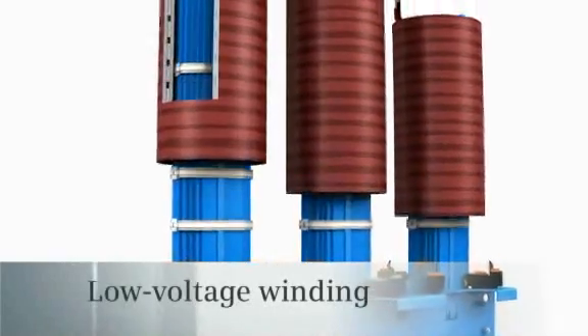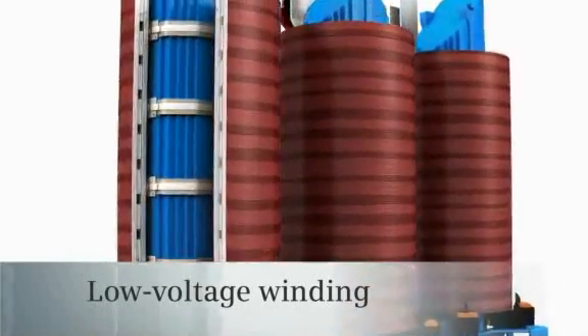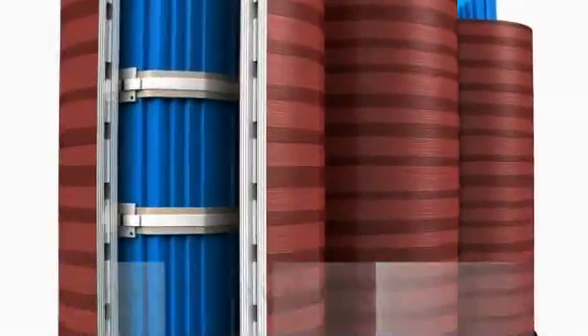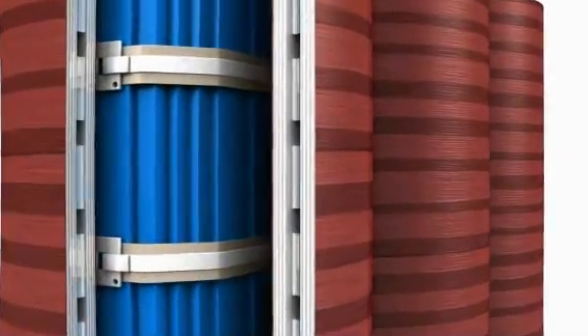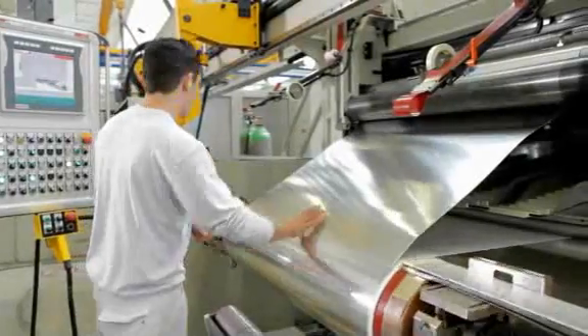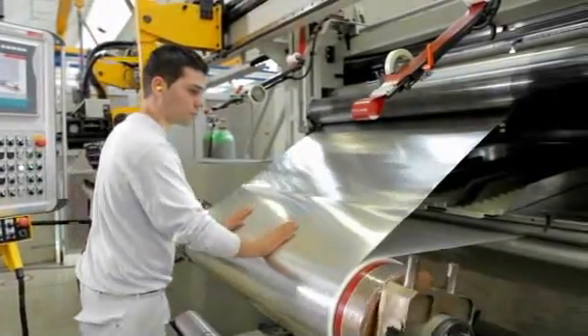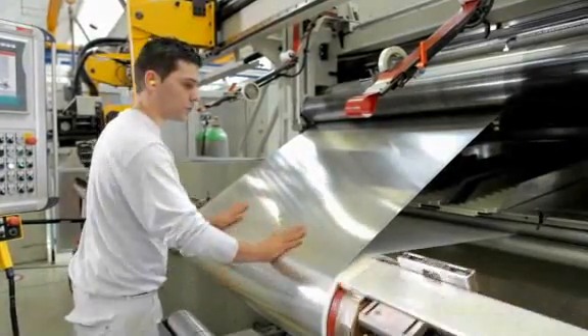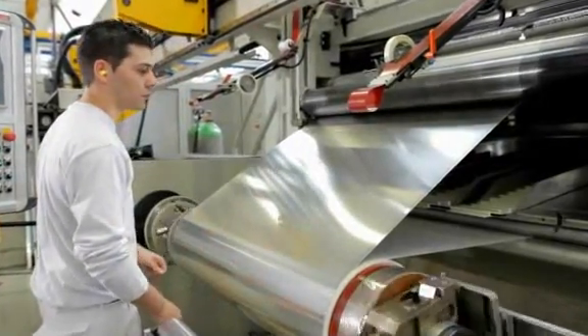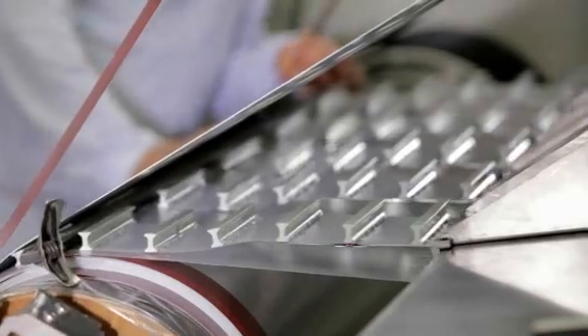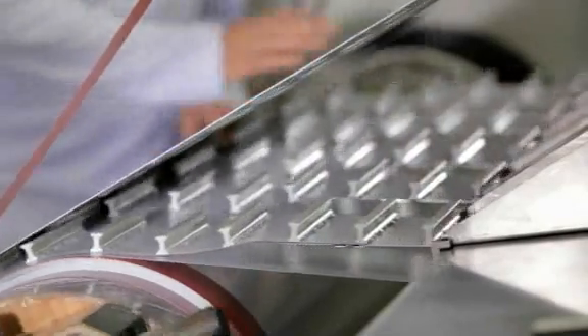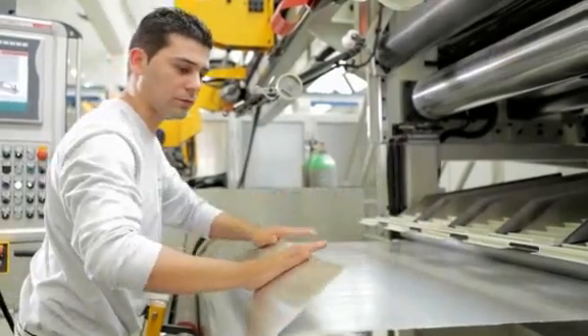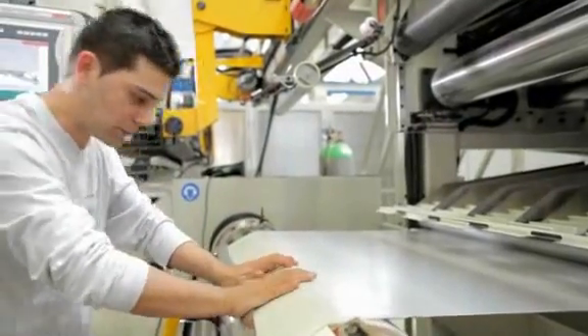The iron core is enclosed by a low-voltage coil. This so-called low-voltage winding also helps reduce the noise level. It is manufactured from a single broad aluminium strip. Due to this construction, the coil remains mechanically stable even under great stress. Spacers provide ventilation channels for better cooling. A fiber-reinforced foil called prepreg serves as a means of insulation.